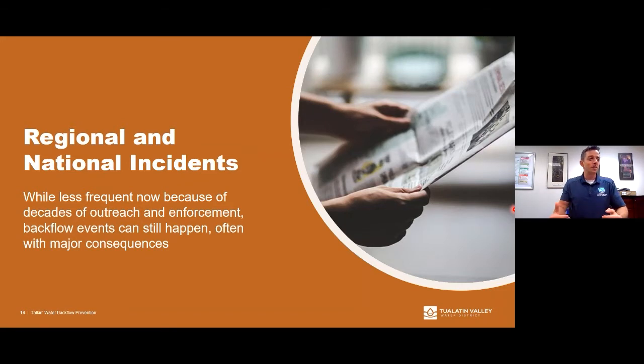Although it seems like we do not hear about many backflow incidents in the day-to-day news, there are actually many backflow incidents reported every year throughout the United States. The reduction in backflow incidents compared to past incidents is a direct result of backflow preventers simply doing their jobs. The more cross connections protected with backflow preventers equals fewer backflow incidents. Most incidents we read about today are actually due to a lack of proper backflow protection or a failed backflow preventer, which was likely not being tested annually.